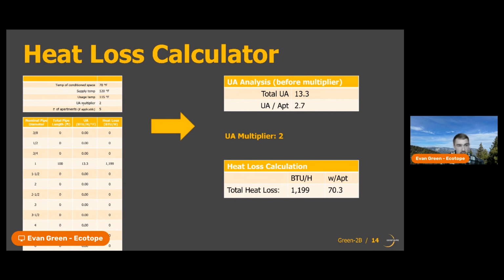Then you can see we have this UA multiplier, which is basically a factor we multiply the heat loss by to account for all of those imperfections in pipe installation. That means everywhere that there's no insulation, and anywhere that the installer's actual pipe routing might deviate from the perfect drawing you have in the design. We also input the number of apartments, and this is basically going to tell us how efficient our design is in terms of how much surface area and how much heat loss we can expect per apartment.